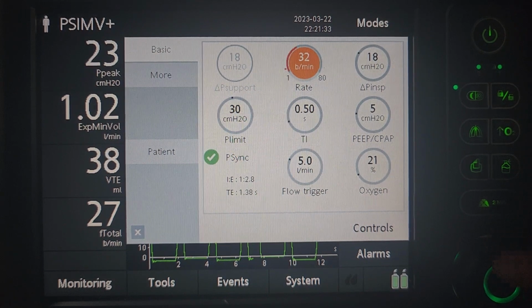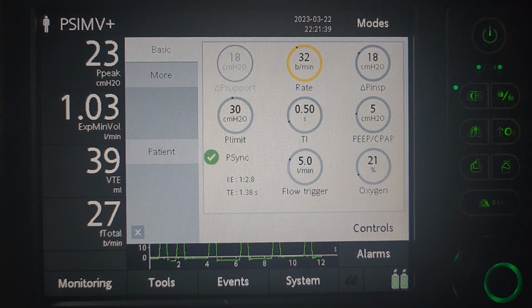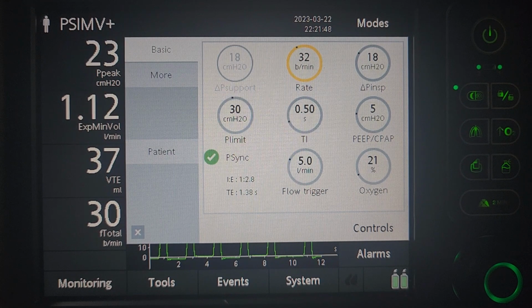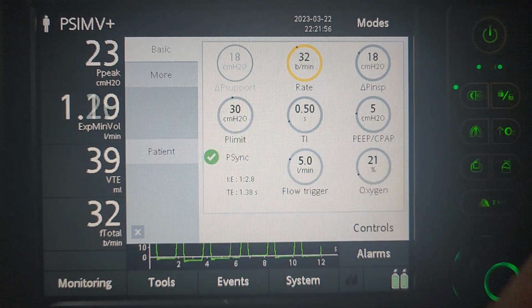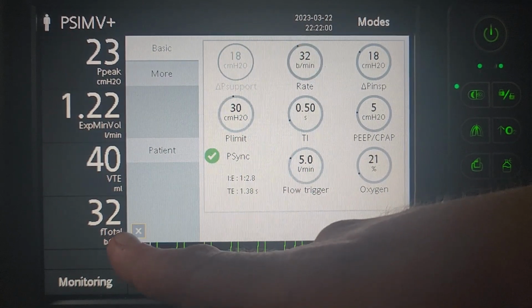Let's go up to 32. Right now we're at 1.02, 1.01 expiratory minute volume. Let's bring that rate up and see what it does, and we can leave it right on this screen and we should be able to see a difference. So right now we're already increasing. Now it's important, if you're going to increase the rate, we try to maintain somewhere close to a 1 to 3 if we can.